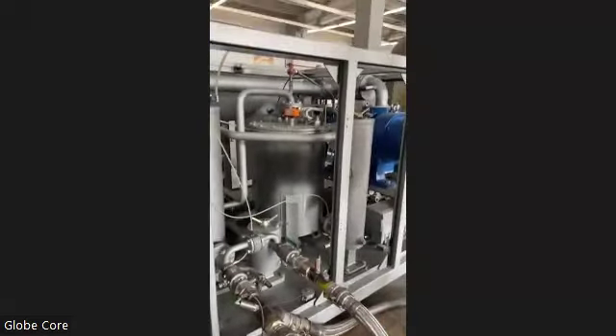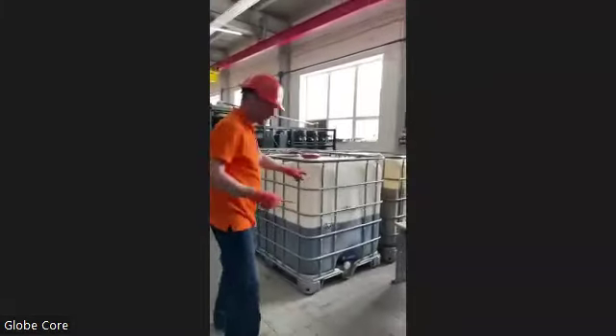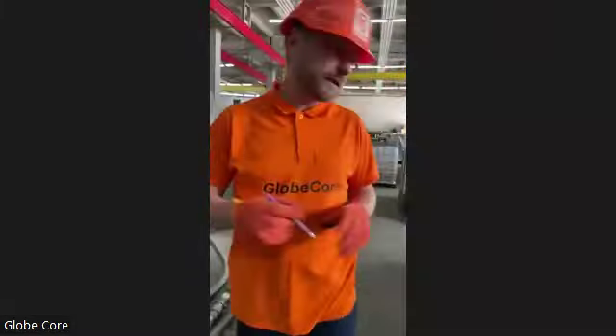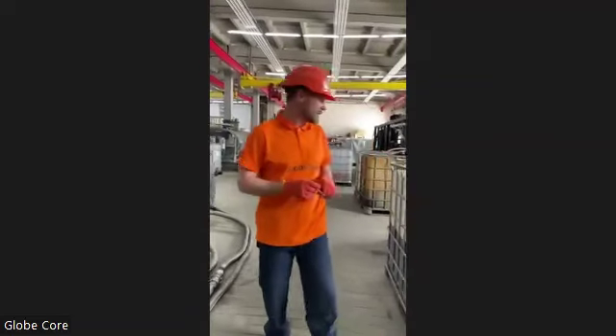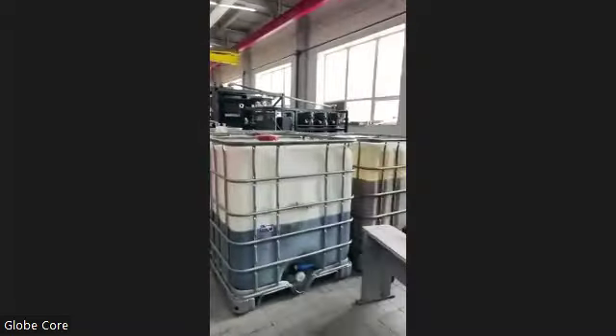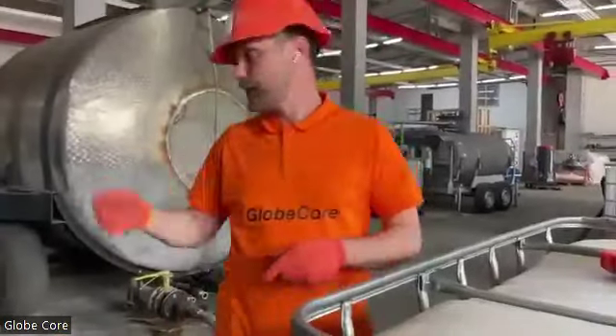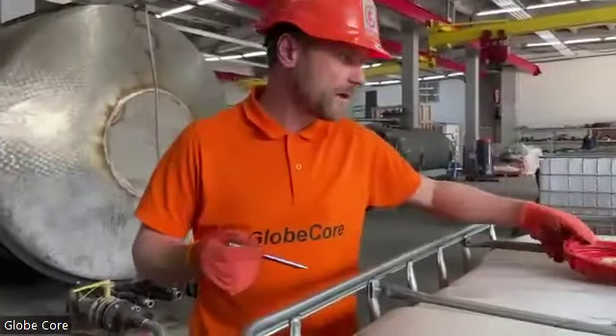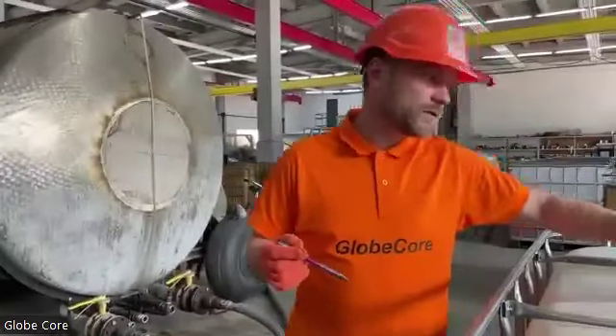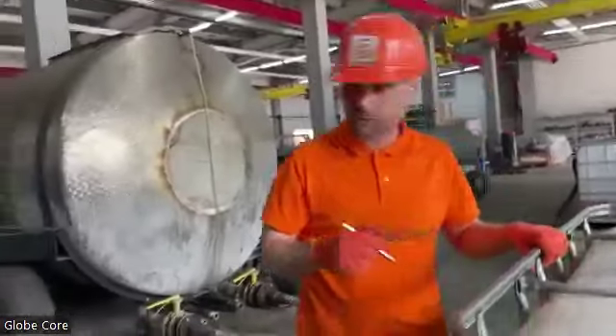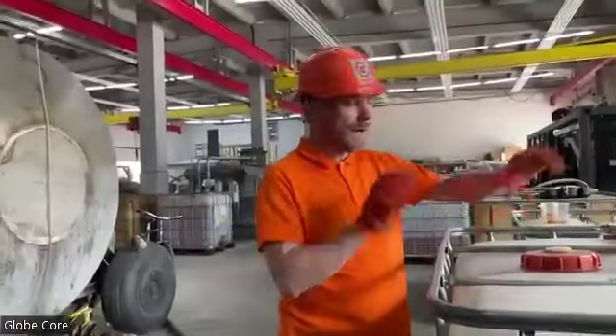Another thing, sometimes while commissioning, we work with a tank like this. And in here, it's quite important to prevent bubbling inside this vessel. Let's say you take oil from the bottom and pass it back through this hole, and oil coming down captures air bubbles, and these bubbles are taken again by the inlet pump, and it will cause significant foaming inside of the vacuum chamber. So make sure that you do not mix in air bubbles by the outlet flow.